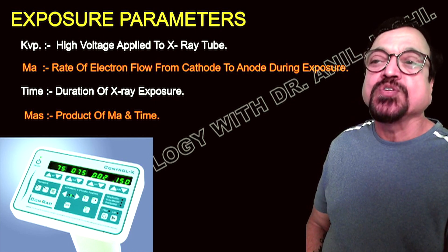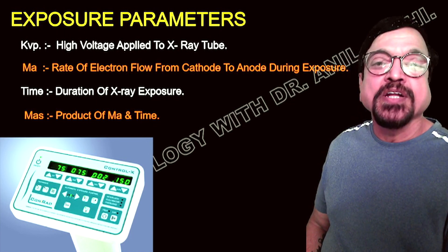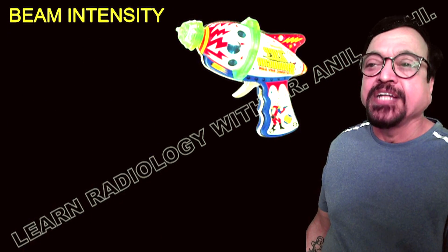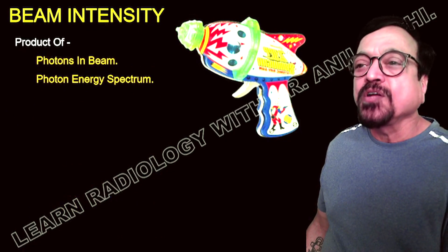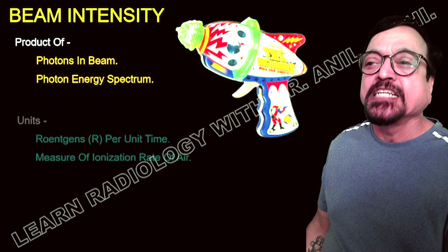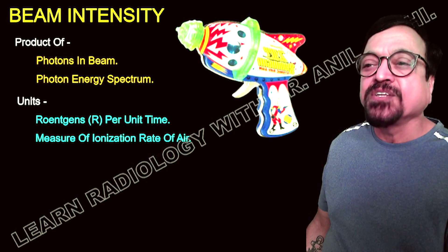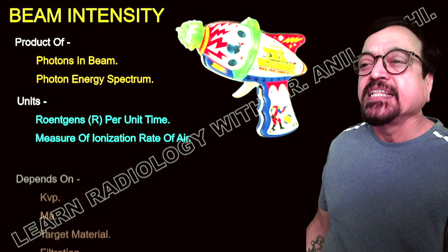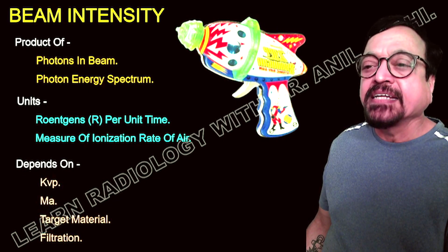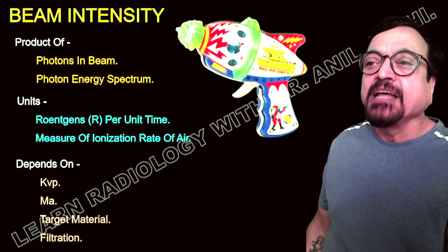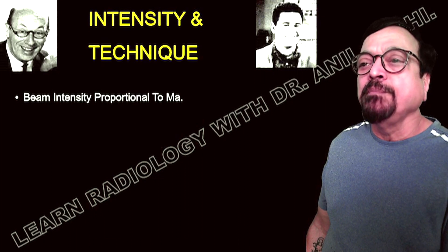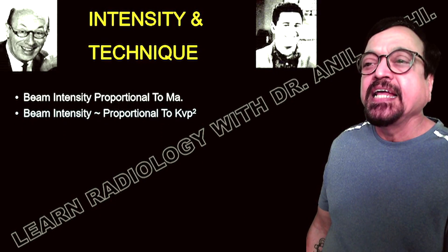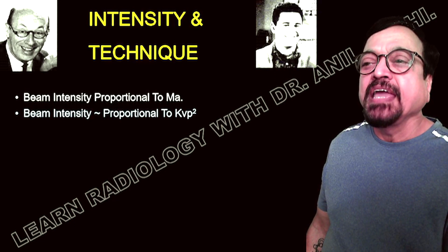mAs is the product of mA multiplied by seconds, which is almost constant for any radiographic part. We have the liberty to increase mA when we want to reduce exposure time. Short exposure timing produces a movement-free or artifact-free image. Beam intensity is a product of the number of photons in the beam and the photon energy spectrum, measured in roentgens per unit time.